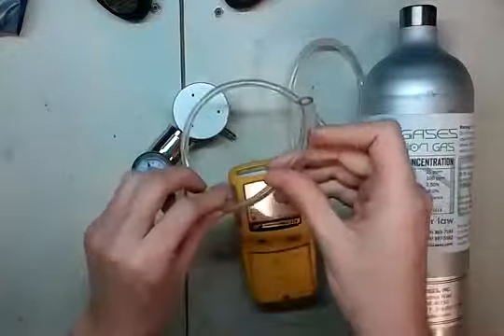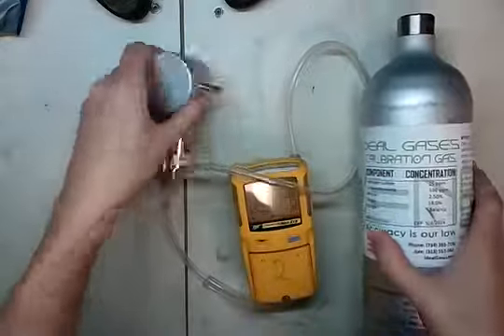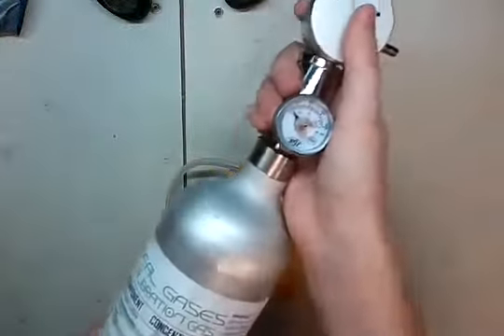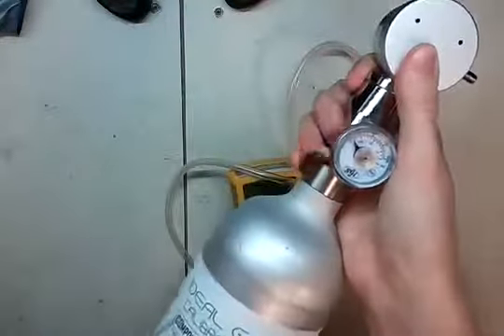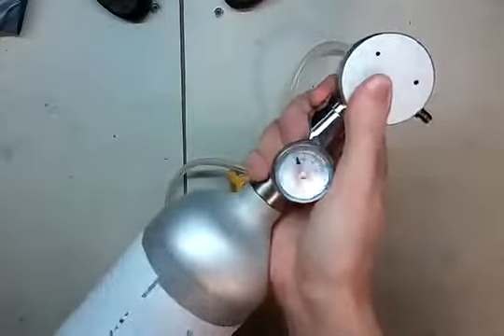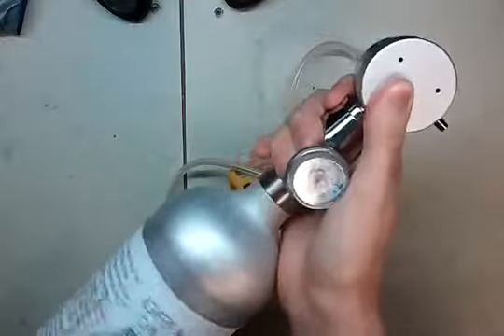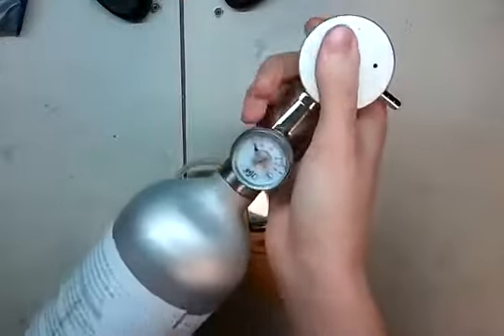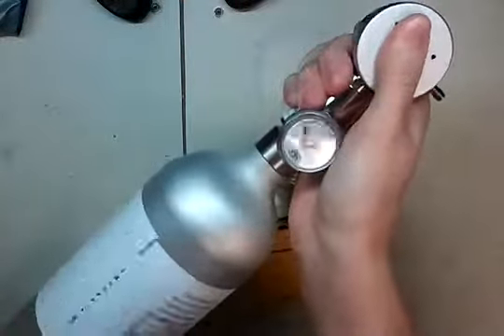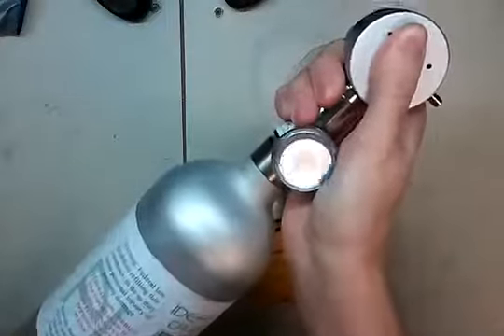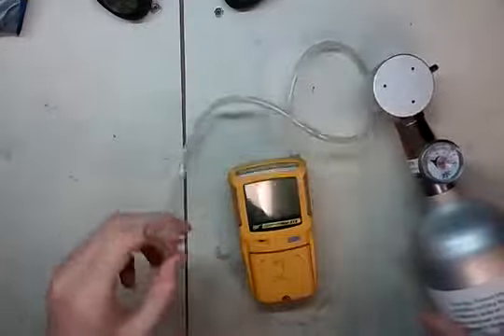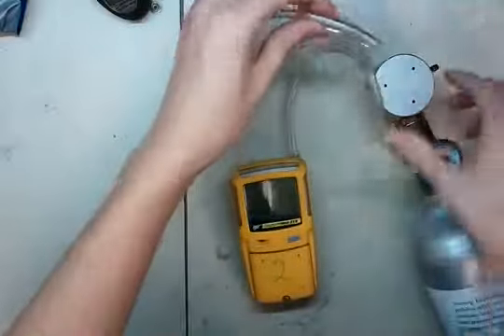So we're going to leave this tubing on here. What we're going to do is take our regulator. This is a demand flow regulator. It doesn't have a knob on the side that turns it on and off. What happens is when vacuum goes on the other end of the regulator, it'll open up the valve. So we're going to insert this here. Okay. You'll hear it click and you'll know that the calibration gas is on. And now we're not going to attach this tube yet.